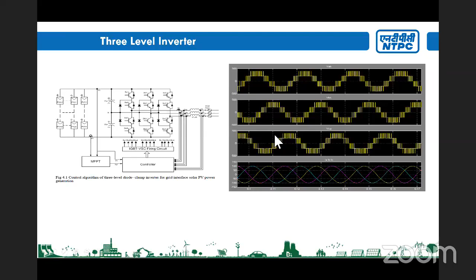Then this is a five-level converter topology. Again, because the level is increased, you can see the number of pulses, that is the switching frequency, is further reduced. With an increase in level, the switching frequency can be further reduced, improving the efficiency of the converter. Maybe with a 2000 volt DC system we are going to have a five-level topology. As of now, there is no five-level topology in the market; mainly only the three-level topology is used. But this waveform shows that with an increase in levels, the waveform tends to achieve a sinusoidal shape.